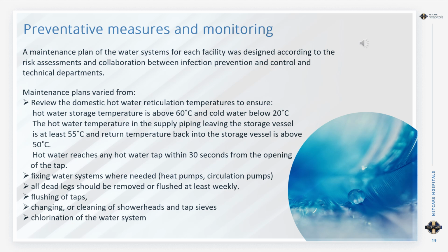Fixing of our water systems where needed. We looked at our heat pumps and our circulation pumps. All dead legs should be removed or flushed at least weekly. Flushing of taps, and this was especially important in low occupancy units. Changing or cleaning of shower heads and tap sieves. And then the chlorination of the water system. So each facility has its own chlorine dosing system that they monitored. I'll now hand you back over to Lilian, who is going to go through the conclusion of our presentation.